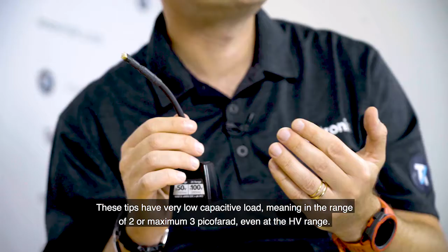Another important thing that we have seen about the tips is the fact that they load your circuit. So the capacitive load is really important to consider. These tips have very low capacitive load, in the range of 2 or maximum 3 picofarad, even at the high voltage range. Another key topic is the importance of respecting the ratings of the signal. With fast switching devices, the rise and fall time goes way below 10 nanoseconds, so the usual bandwidths, 200 MHz, 350 MHz, may no longer be enough. You may need to extend the bandwidth of your measurement system.